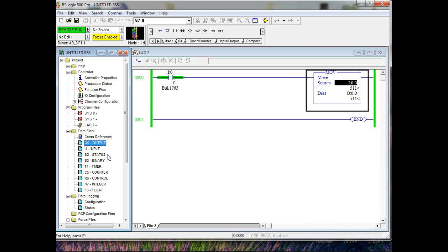What is an integer? So counters use integers. A whole number without a decimal point. There's no fractional portion of an integer. It can be signed, so we're dealing with signed integers. Counters use signed integers. Timers can use floating point numbers because we can put a fraction in it if we choose a small multiplier. Now, I think it does the multiplication on the fly. I think it's integers too, because we enter the number in integers.